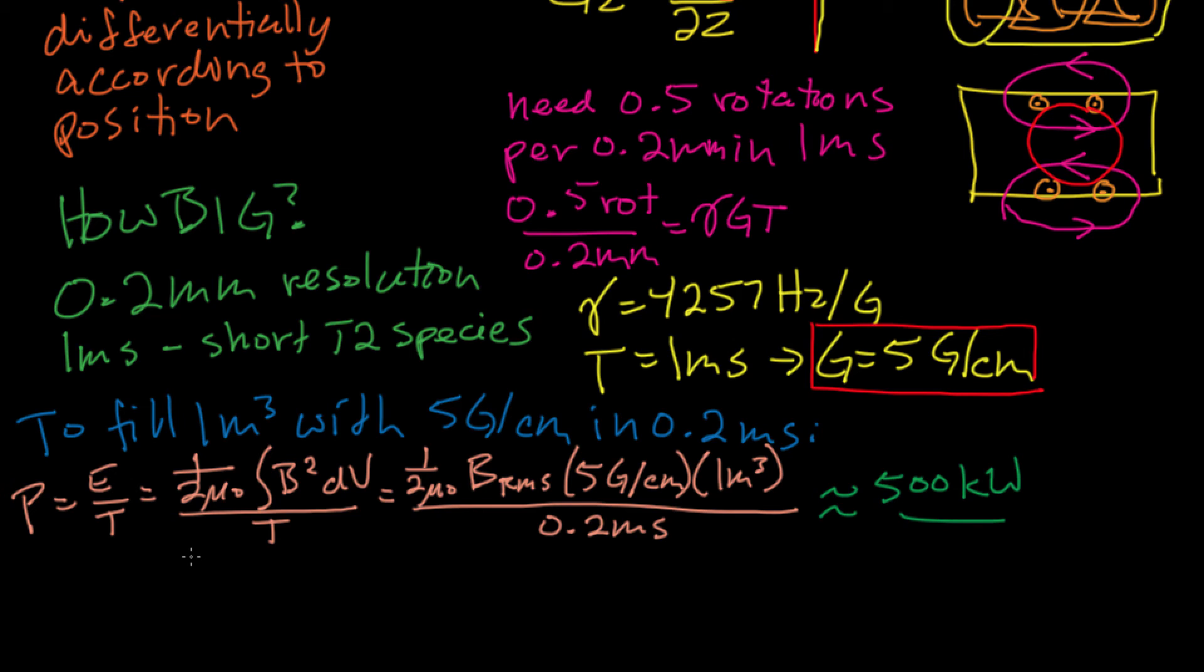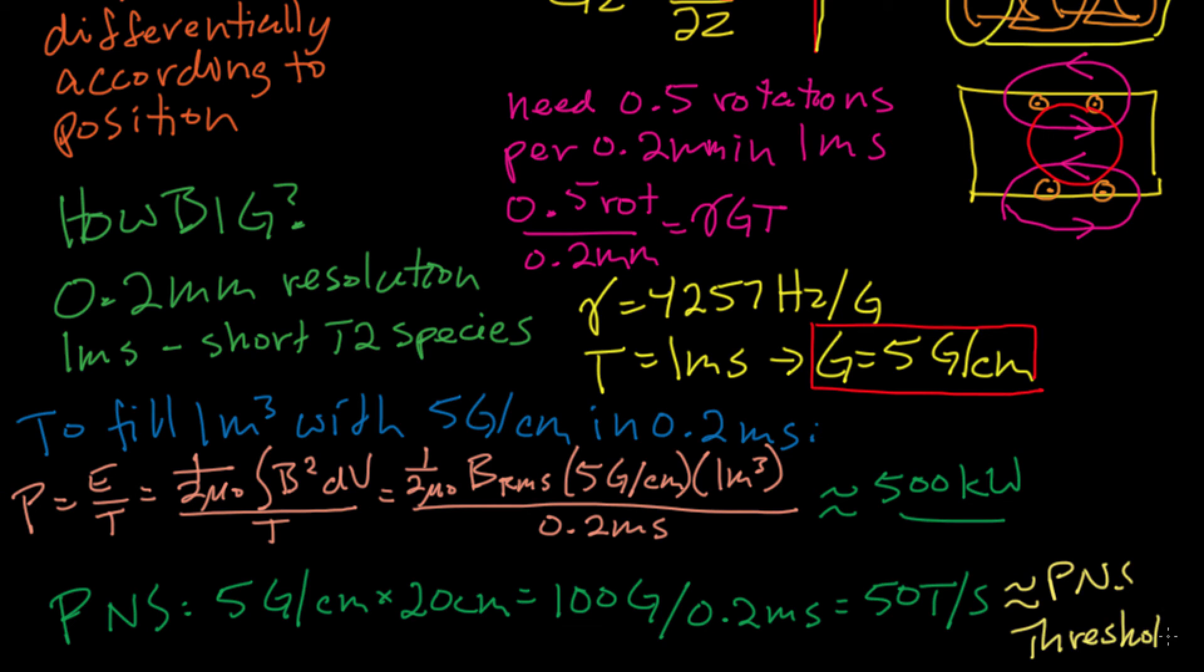Now interestingly, there's another more physiological limitation on how fast you can switch gradients. Rapidly switched magnetic fields induce EMFs, and those EMFs can create currents in the body, and those currents can generate peripheral nerve stimulation, which can cause tingling sensations and twitching. So that's not good. So if you've got a 5 gauss per centimeter gradient, at the edges of the body, which are about 20 centimeters away, you have about 100 gauss of magnetic field. If you're generating that in 0.2 milliseconds, the magnetic field slew rate's about 50 tesla per second. And it turns out that physiologically, that 50 tesla per second is right around the threshold for peripheral nerve stimulation. So it just happens that peripheral nerve stimulation sets thresholds that are just about the same as the current engineering limits.